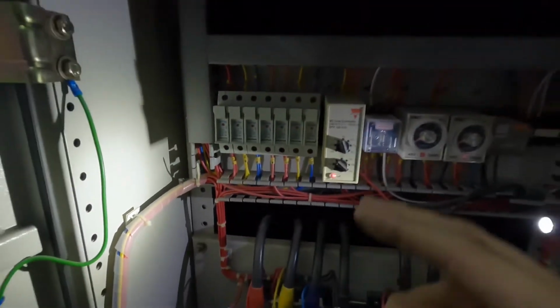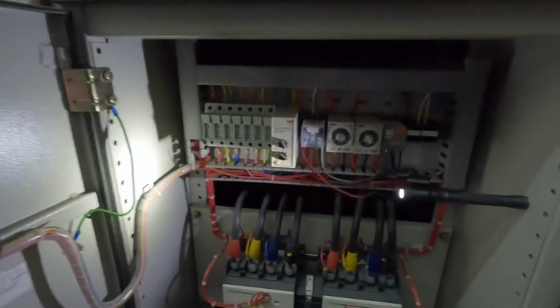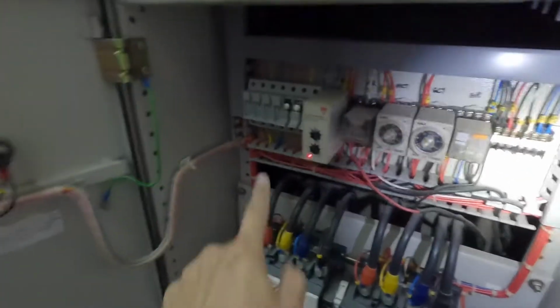Okay, now we need to check this ATS panel whether it can run automatic or cannot run automatic. We don't know. We want the UVR relay to do the calling. In order to do so, first of all, let's identify the genset fuse. Genset fuse, the one with G. I open the fuse first because I don't want power interruption change over when the genset runs. Now I have opened the genset fuse, so when the genset runs, the power supply cannot come here, but I just want to know whether it can call the genset to run or not. Then I'm going to trigger this UVR relay and see whether the genset can start automatically or not.